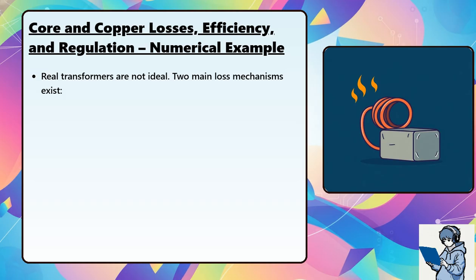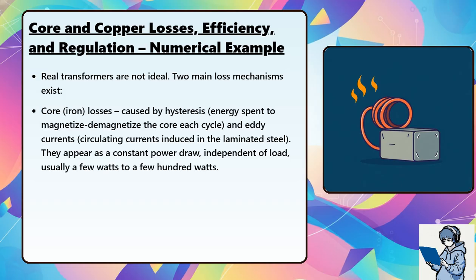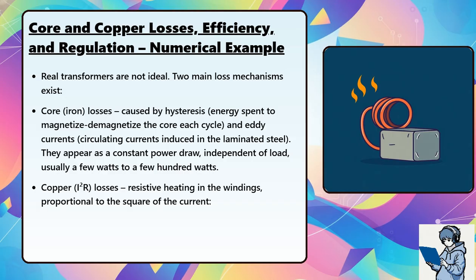Two main loss mechanisms exist. Core iron losses are caused by hysteresis, energy spent to magnetize and demagnetize the core each cycle, and eddy currents, circulating currents induced in the laminated steel. They appear as a constant power draw, independent of load, usually a few watts to a few hundred watts. Copper I squared R losses: resistive heating in the windings, proportional to the square of the current. P_cu equals I1 squared R1 plus I2 squared R2.